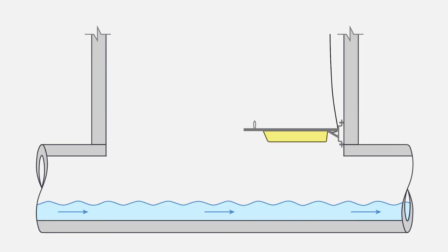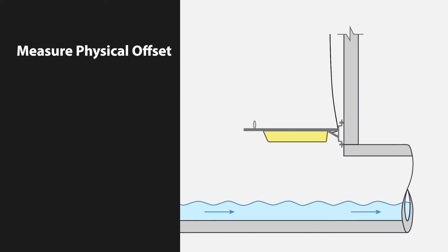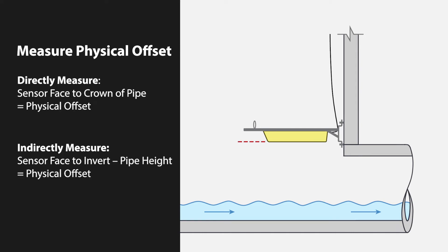Once the sensor is positioned on the wall mount bracket, measure the physical offset of the sensor, the distance between the face or bottom of the sensor and the crown of the pipe. There are two methods of measuring this distance: directly or indirectly. It may be easier to measure the physical offset indirectly.